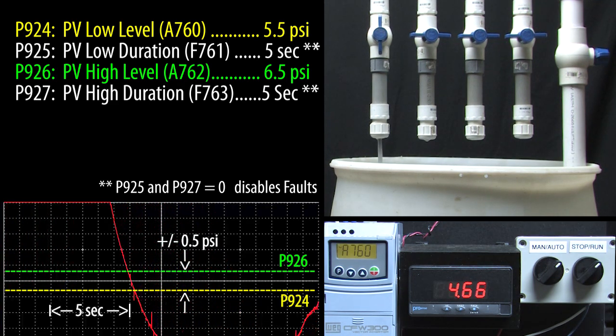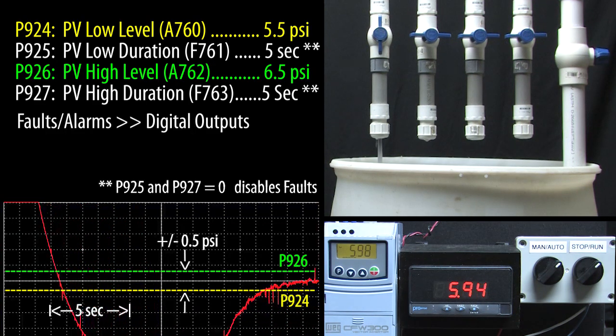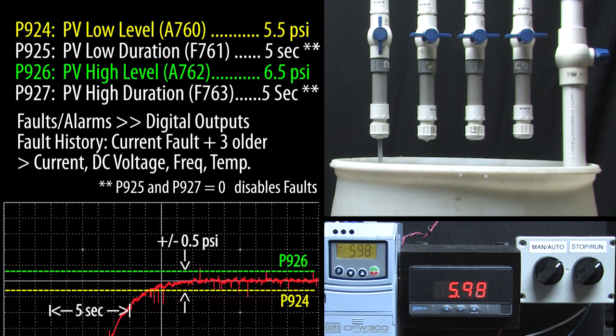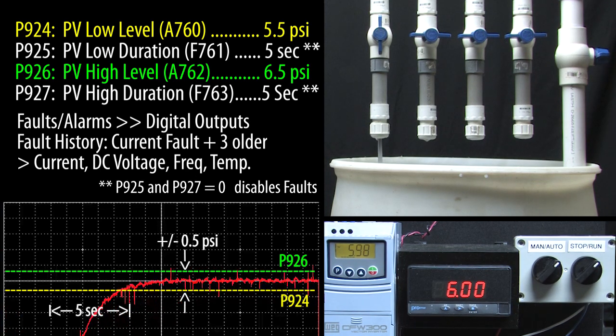That's all we need to know about PID generated alarms. Of course you can always set up digital outputs to report different kinds of alarms and faults, and you can view the current fault and the three previous faults at any time along with the current, DC link, frequency and temperature present when the last fault occurred.